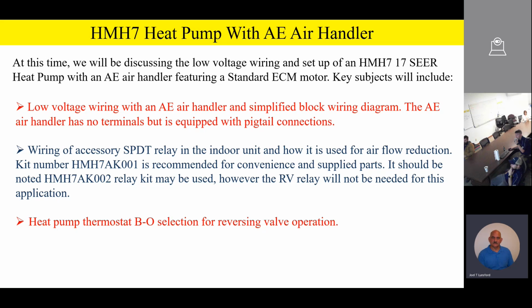Now, we want to make sure that the heat pump thermostat that you select has a B/O selection for reversing valve operation, because we're going to learn here shortly that the HMH7 heat pump utilizes the B terminal. Let me say it again, the B terminal for heating, which is exactly opposite of our other Champion products. So our other heat pump products, we use the O terminal for cooling. On the HMH7, we use the B terminal for heating. It's not bad, it's just different, and we just need to remember that. We also need to remember that our heat pump thermostat has to have that selection so that we can select B or O for reversing valve operation.